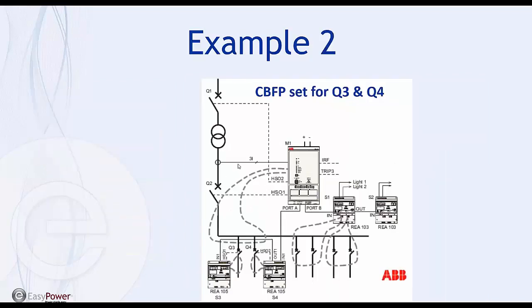Now let's look at another example. Same as before, pretty much. Protecting a transformer, a single bus. Here, what we're going to do is use extension units now, and we're going to use the REA103, which does not have the selectivity, and then on this portion of the bus, we'll use the REA105, which does provide the selectivity. So you have the loop sensor that wraps around the bus for the main, and then the REA105 extension units are protecting the feeders. And then the REA103 protects the bus, breakers and terminations.